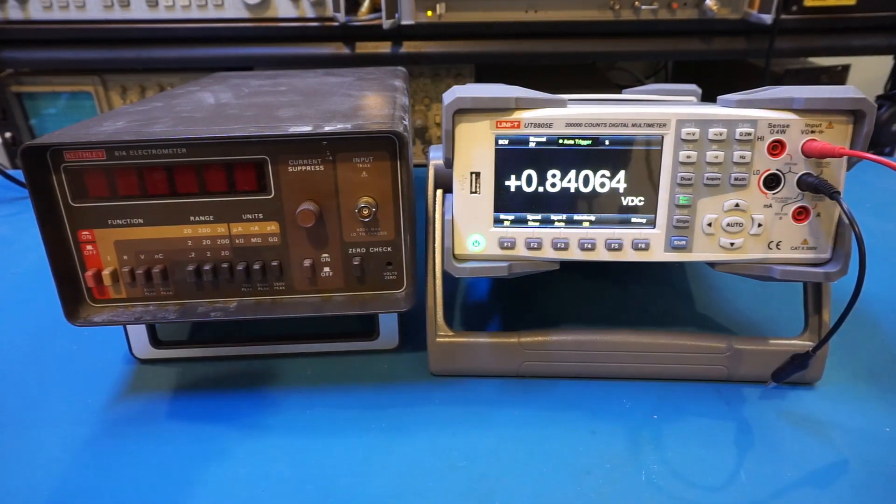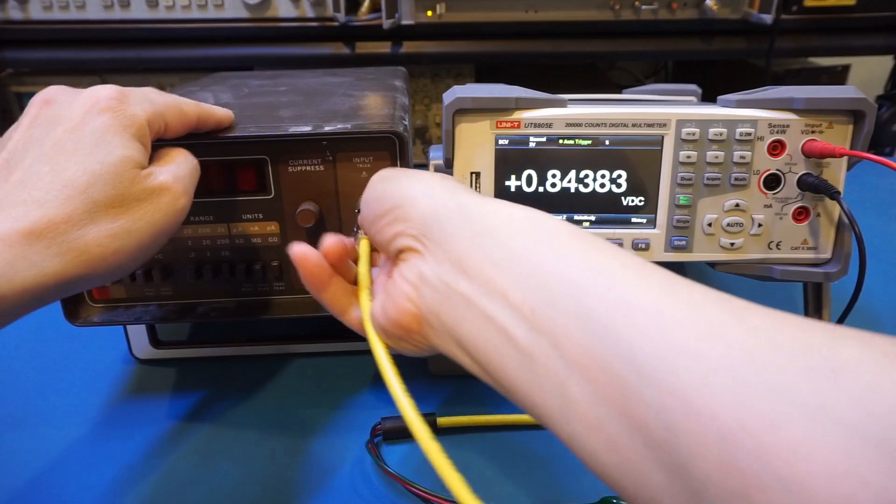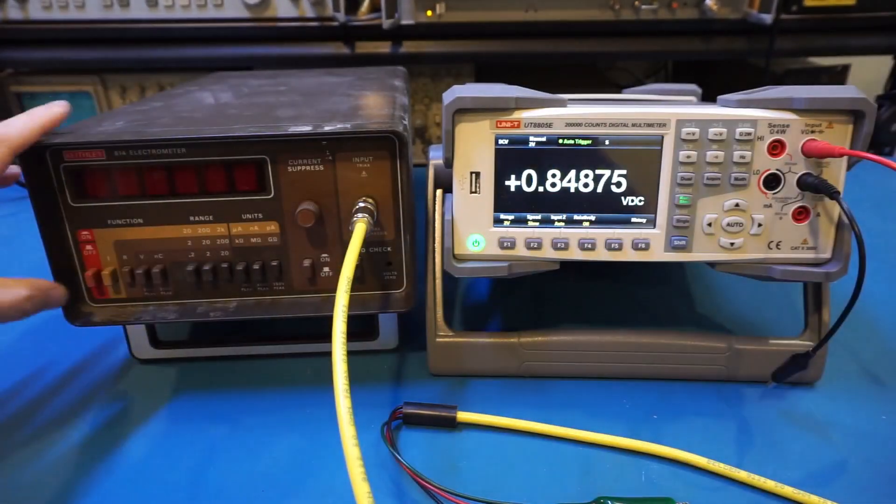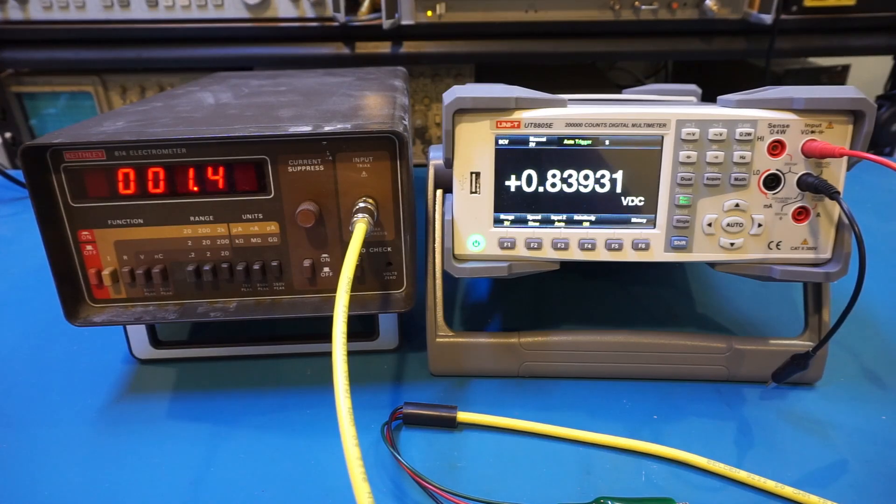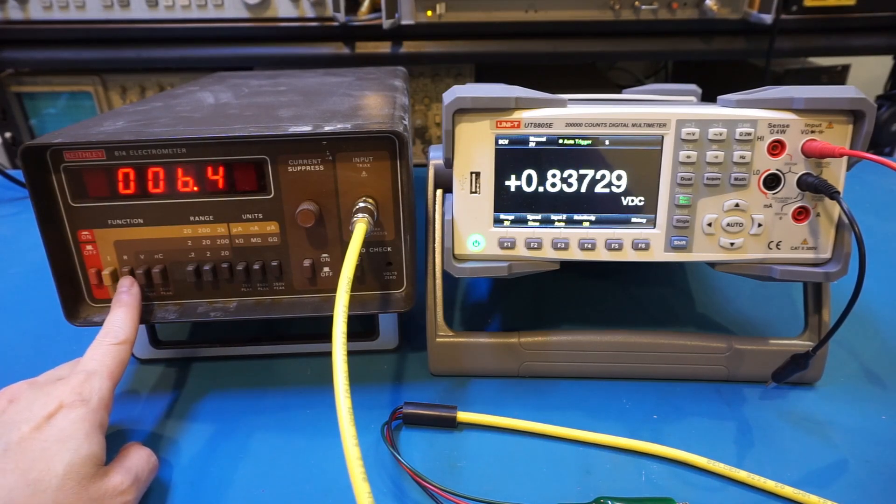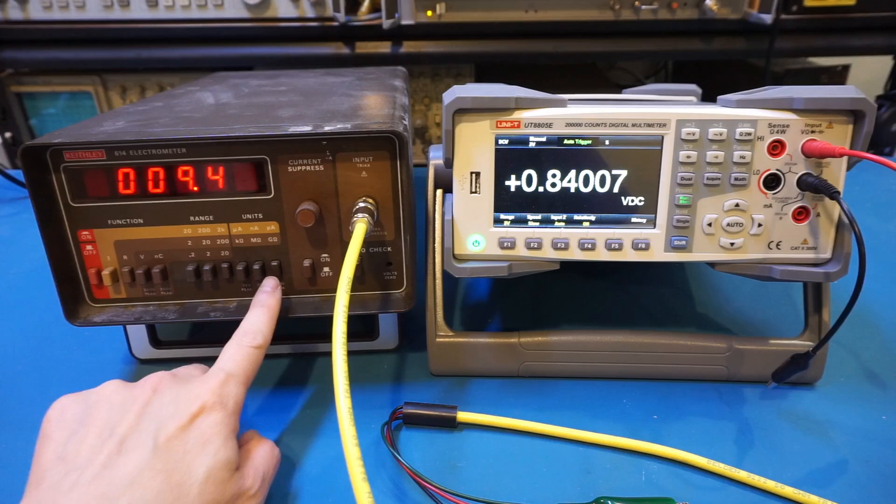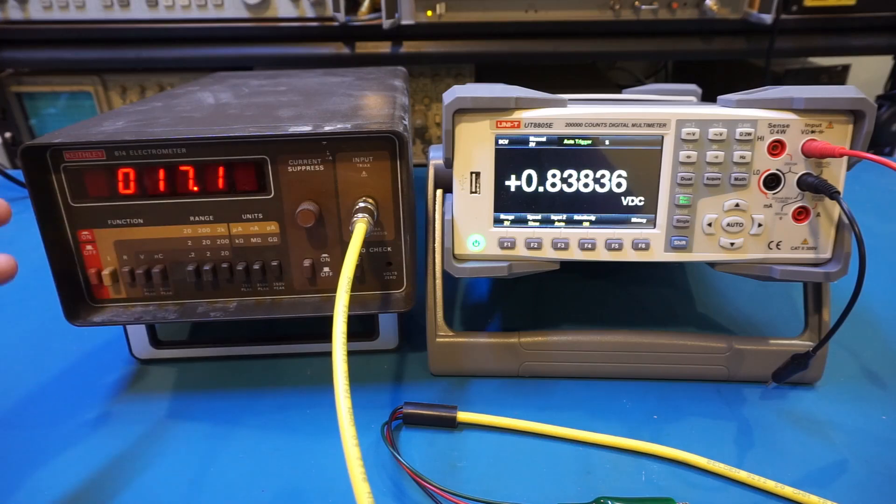And now let me connect the triax to the Keithley 614. And we'll power it on. And you can see we are already in resistance measurement mode. Currently, the range is 20 gigaohms. So that is actually all set. And you can see that without anything connected, the reading is increasing as it is trying to measure the resistance.